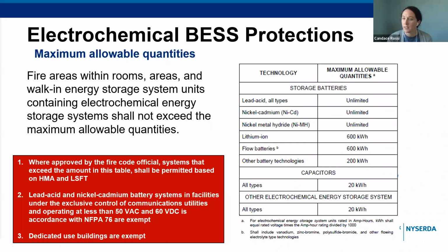So this slide here is for the maximum allowable quantities. So this represents the maximum allowable quantities that were discussed earlier in the presentation. If an installer wants to exceed the values listed in this table, they will need to conduct the hazard mitigation analysis and the large-scale fire testing to show that the system will still be safe.